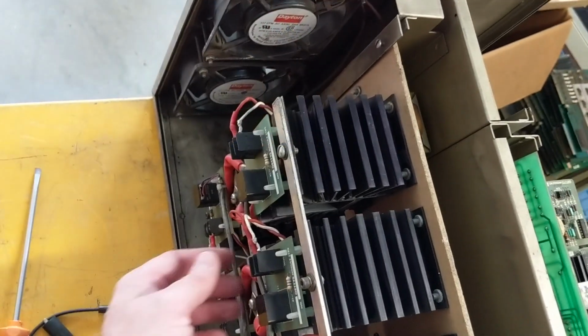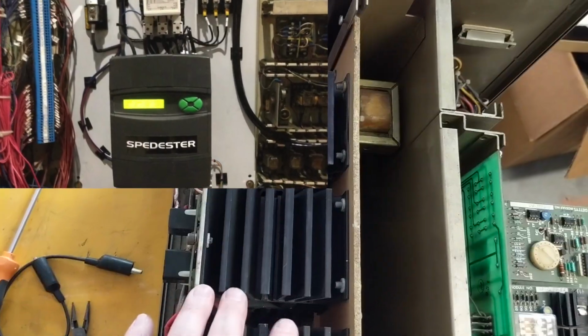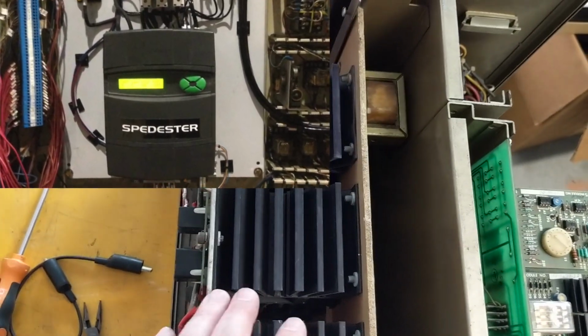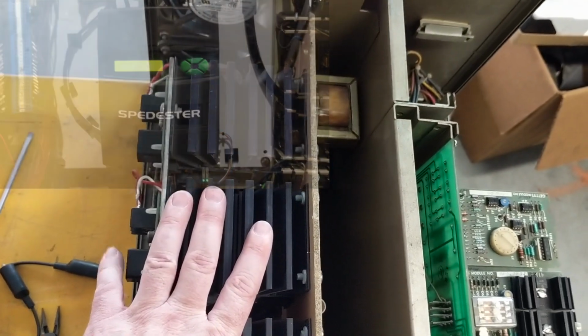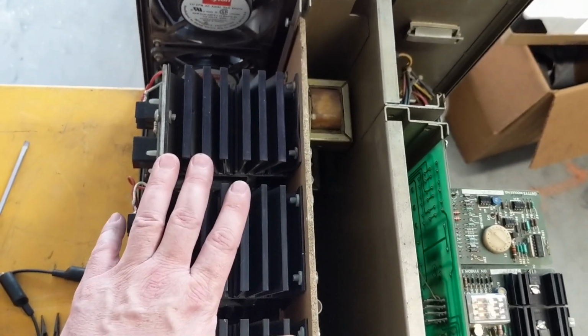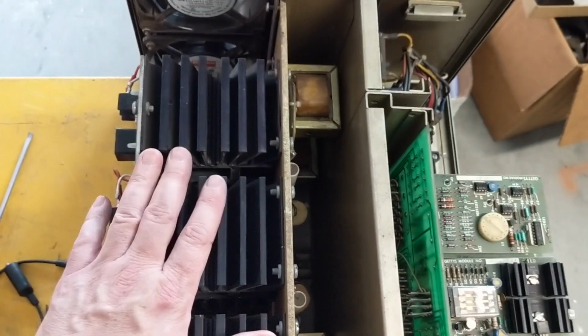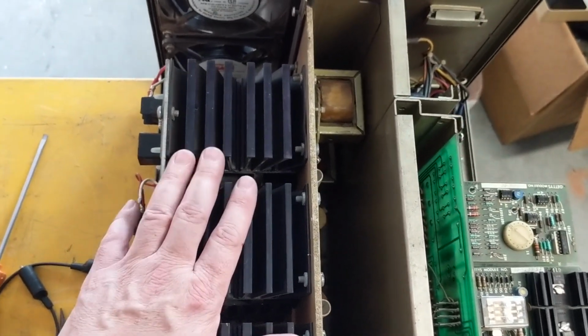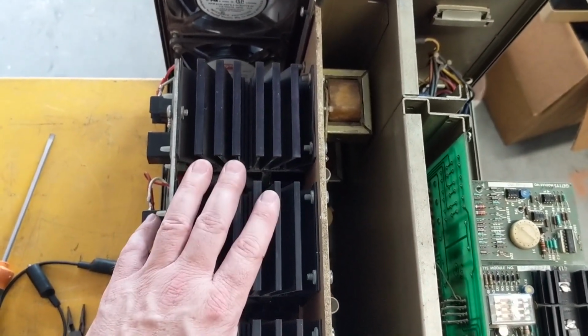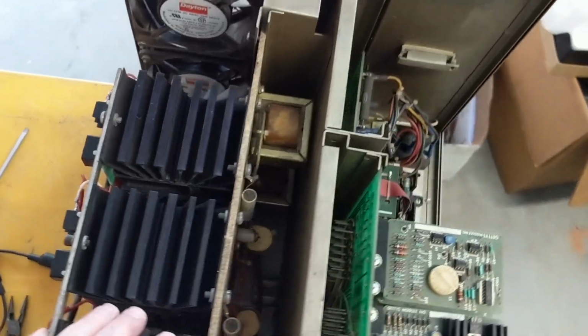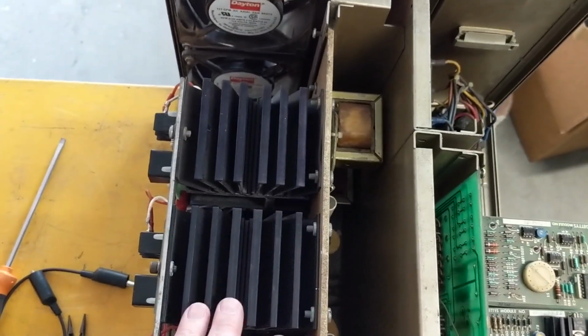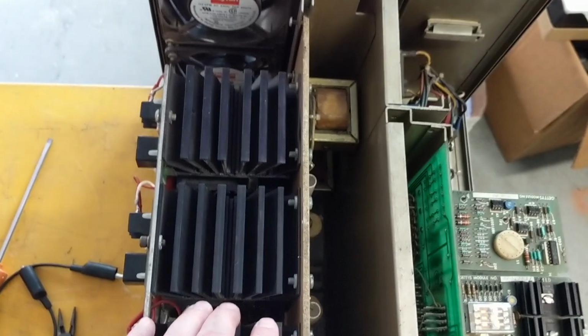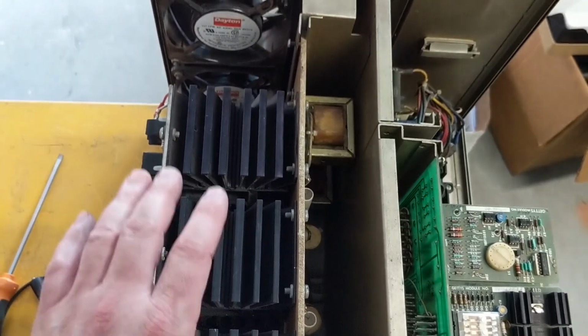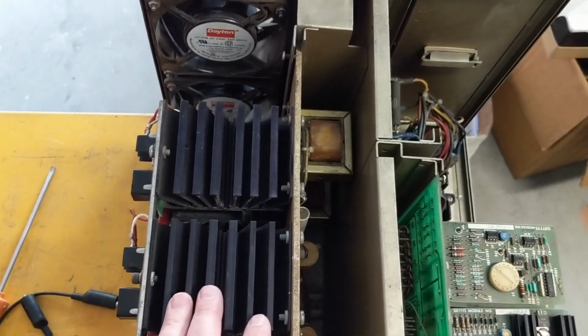And the drive pictured above is a pretty neat digital DC drive, where it actually will do the field weakening for the 4,000 RPM motor that's needed for the 20V CNC machine. A lot of spindles on the CNC machines are similar, where the field weakening goes down really low in amps on the field to overspeed the motor. I know the 10V and the 20V both have a 4,000 RPM motor.